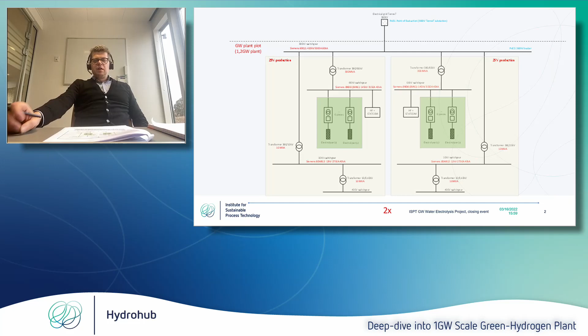As you also see in the single line diagram, briefly touched on by Nick, it could also comprise equipment not directly connected to the power converters—due to the choice of power converter, you could end up needing harmonic filters, capacitor banks, shunt reactors, or other kinds of compensation equipment. I'll come back to that in a couple of slides, but wanted to make people aware. Could I have the next slide?